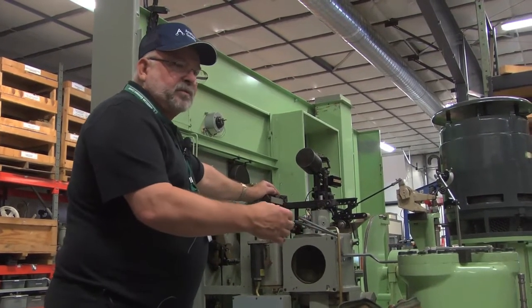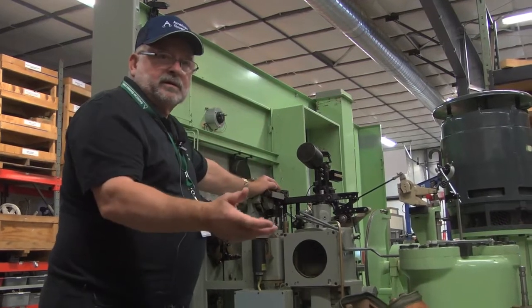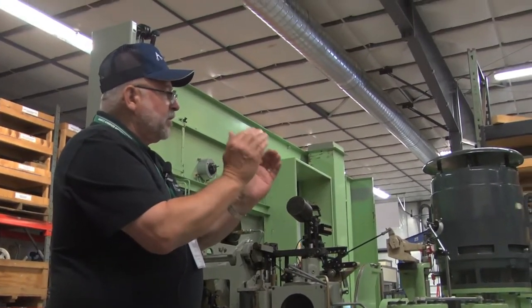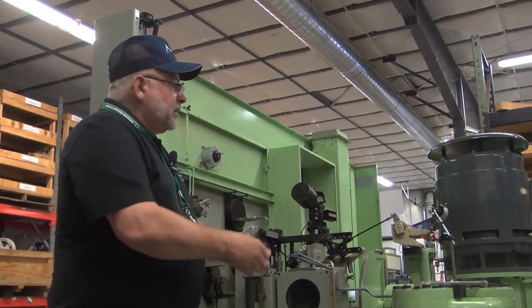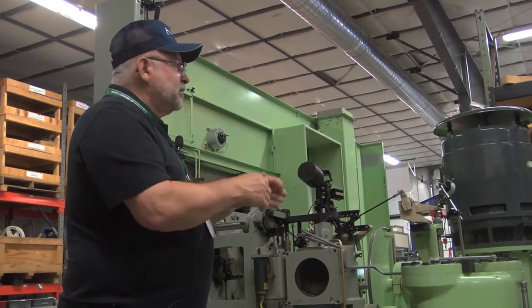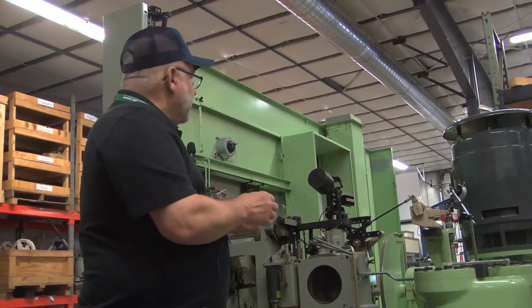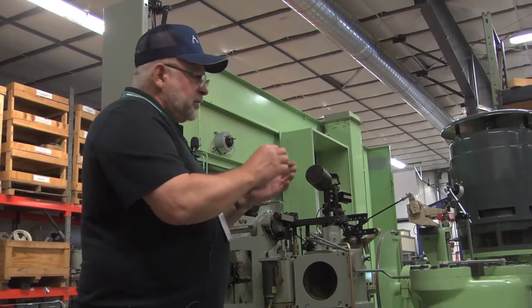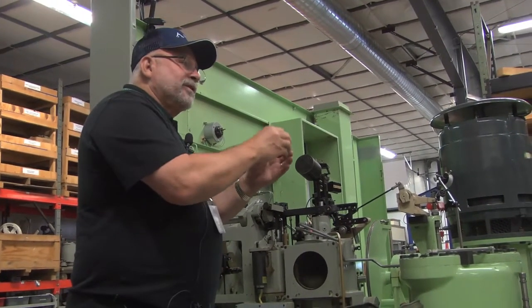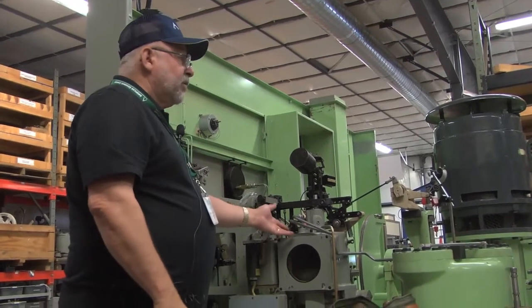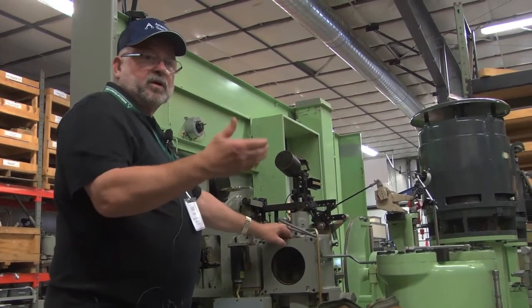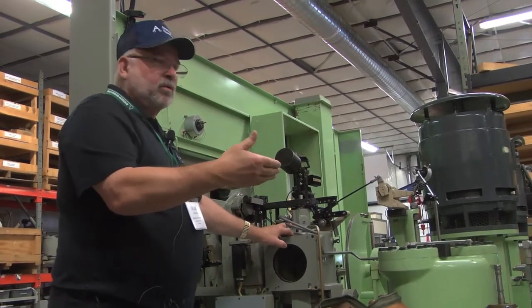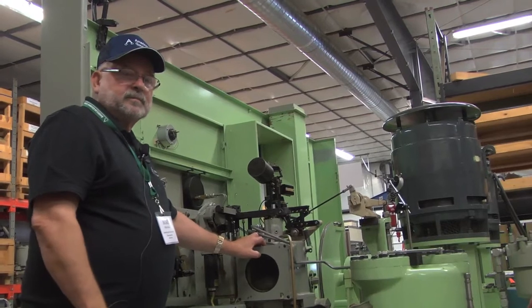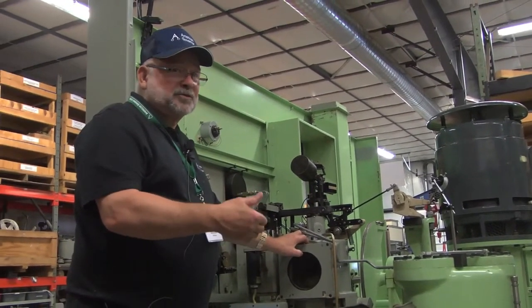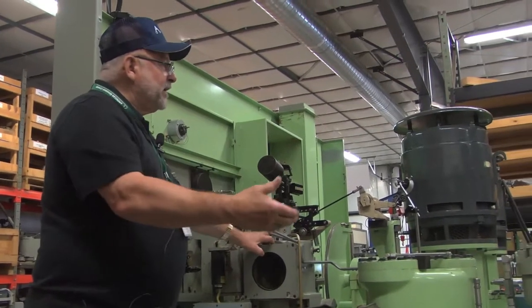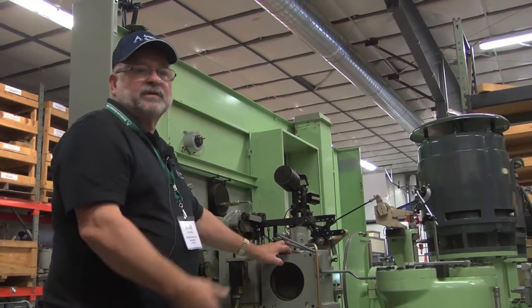And the Pelton is designed where you can pull the rotor out without a tool. It's got magnetic keepers on the front of each one of the poles, whereas a Woodward has to be all kept together, because once it goes clunk, you demagnetize it. So on a Pelton, I'll try to find a Pelton rotor here, and I'll show you. It's just like an extra cover on the front of each one of the poles. And they have them in different configurations, 4, 6, 8, 12. And your book will show on your PMG how many poles you have on your particular unit. Sometimes, just like all manuals, they get a little generic and they'll just stick something in there that may not be exactly what you have. You know, it's just a picture of it for you to see.